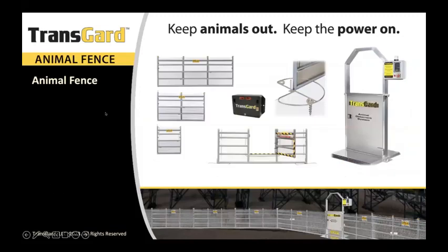We have a modular design, as I mentioned before. The advantages: there's no outage or digging into the substation to anchor the fence. It only goes in about 6 inches below the gravel and is then covered up to the bottom rail by gravel.